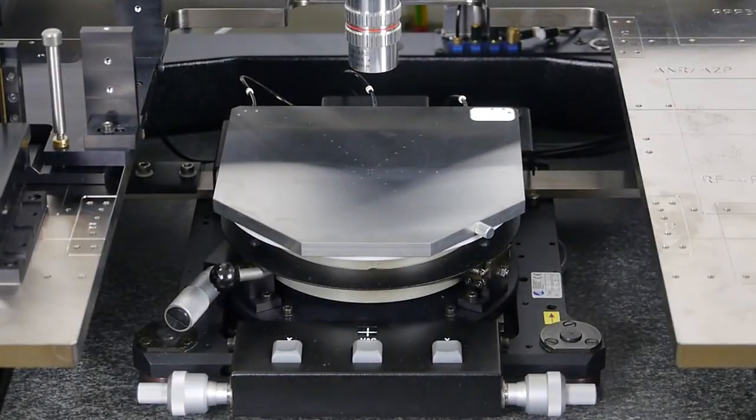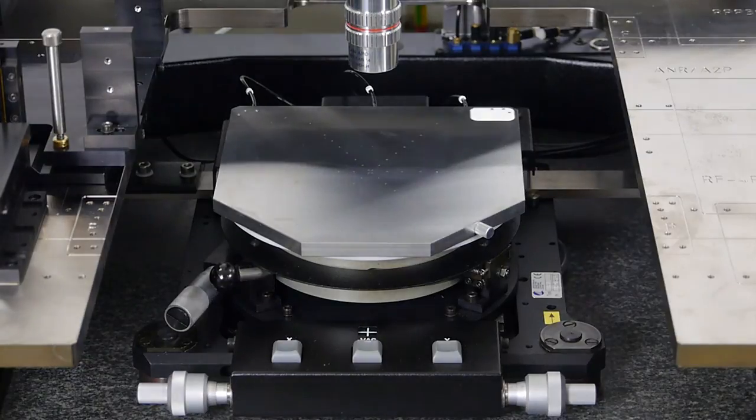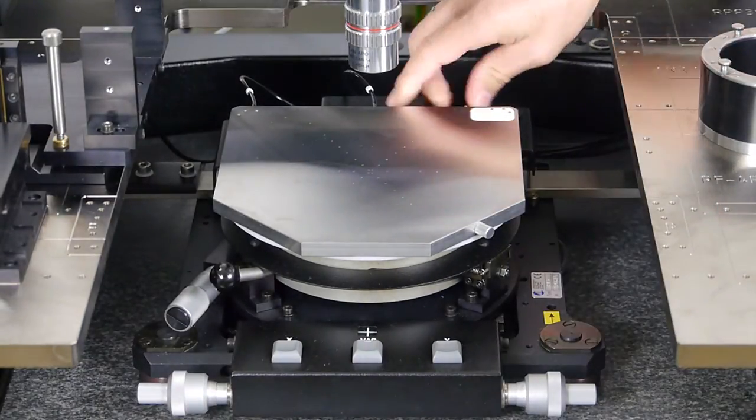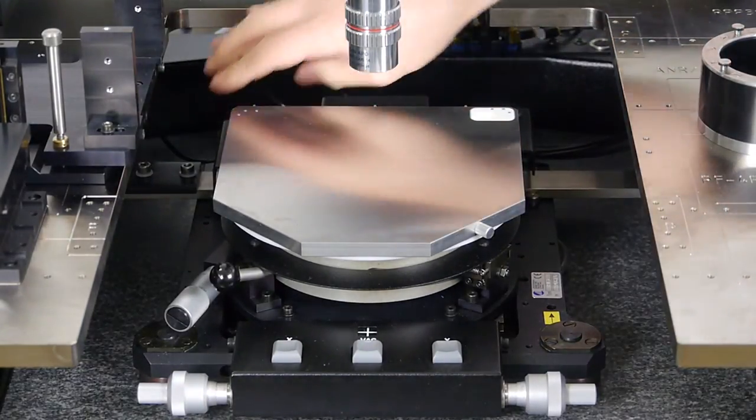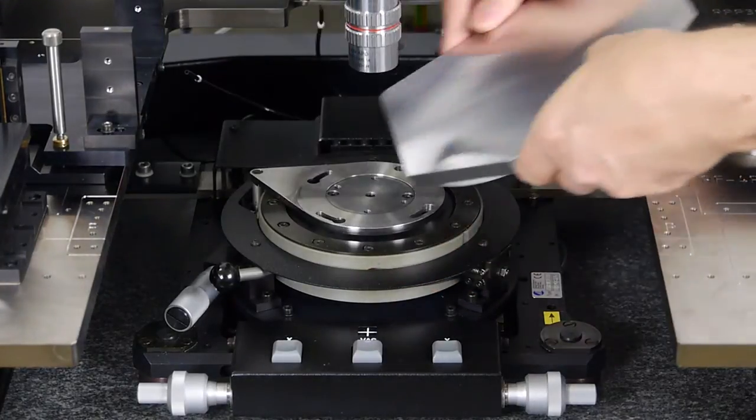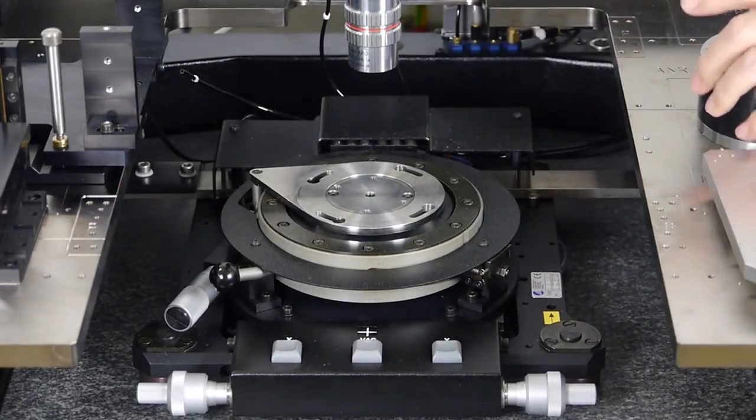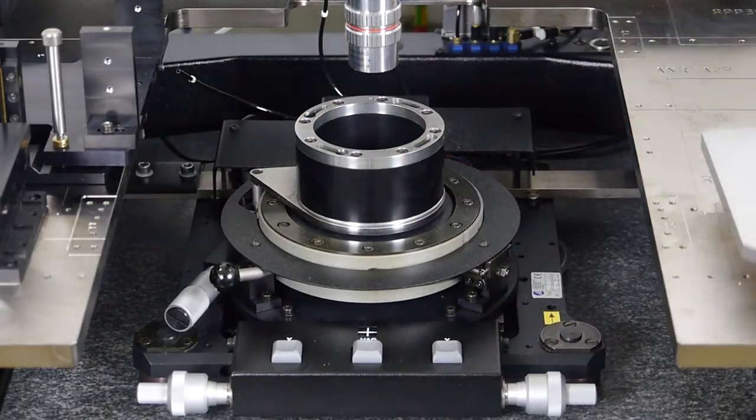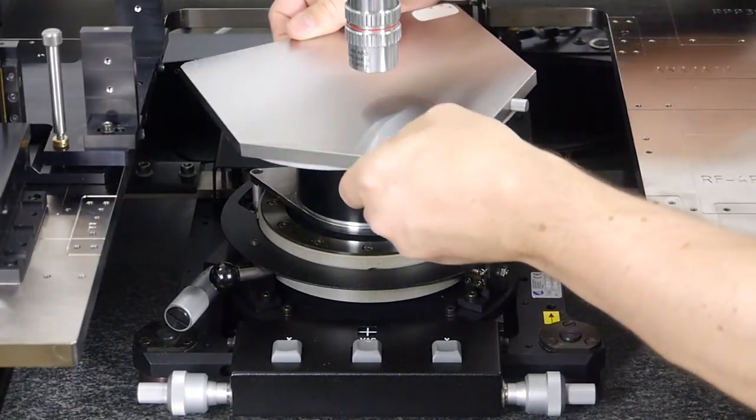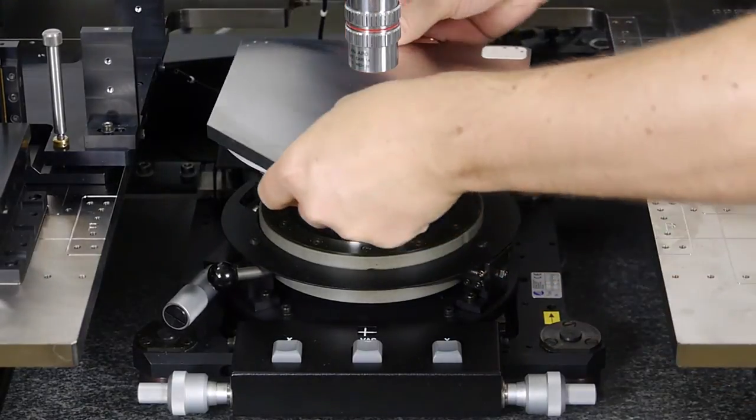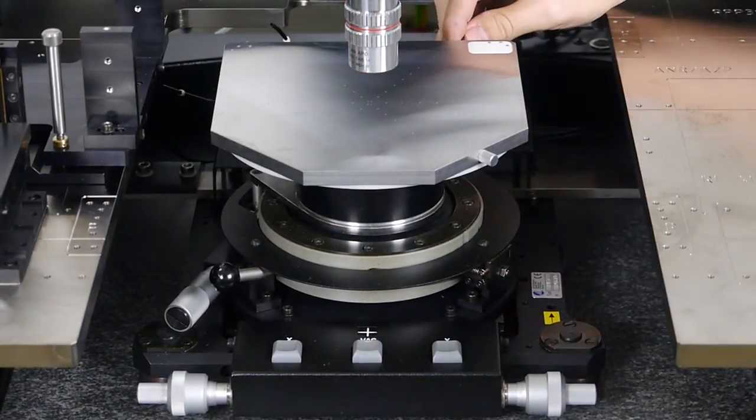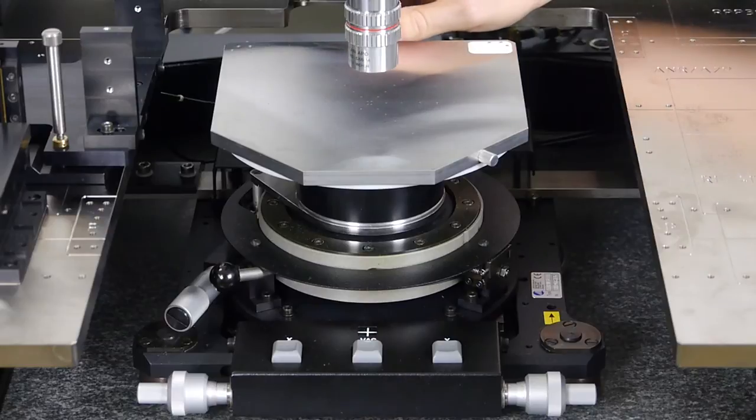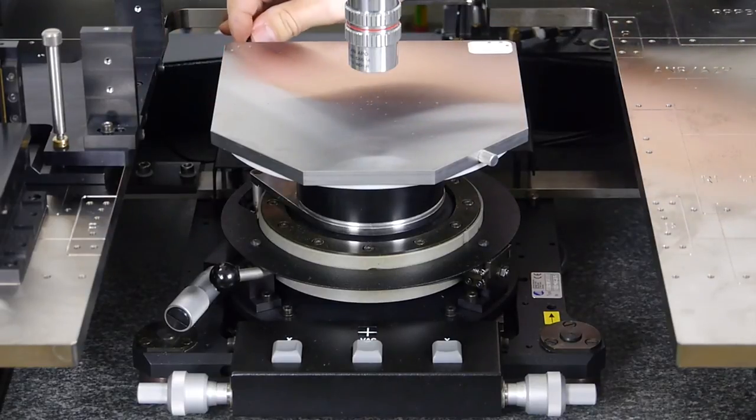We start with the mounting of the chuck raiser under the chuck. The stage offers a very easy Bayonet system for this, so no tools needed to mount it. Finally, connect the vacuum tubes for the main and auxiliary chuck vacuum. That was easy.